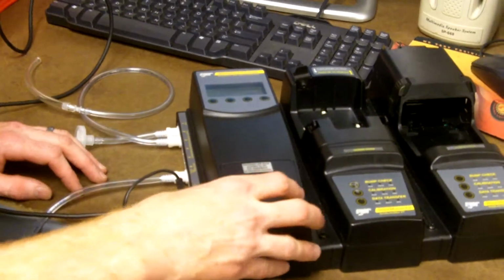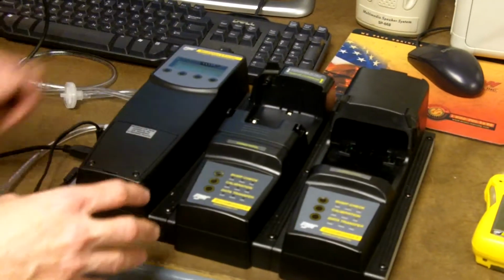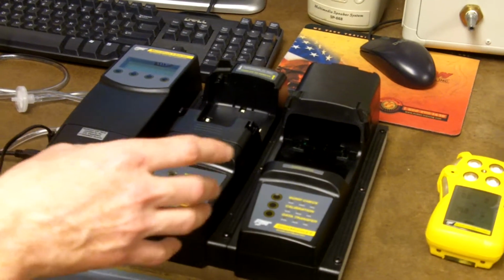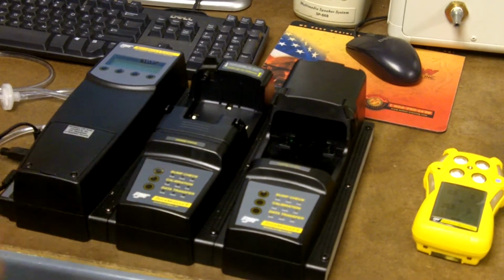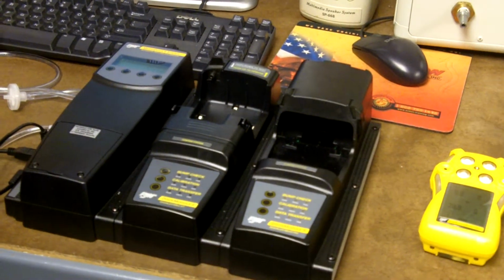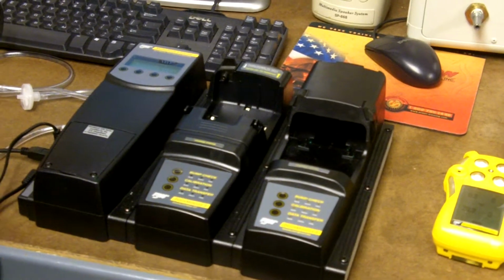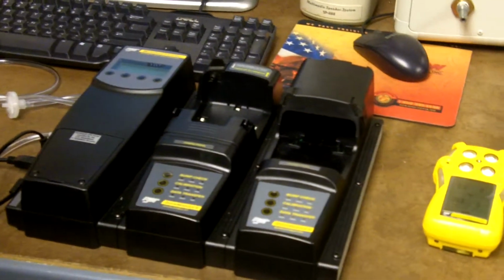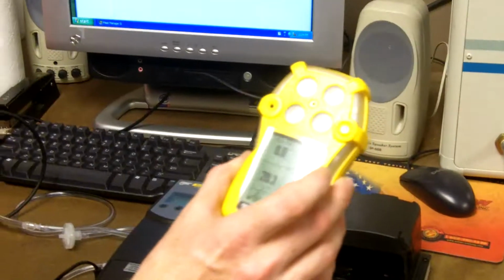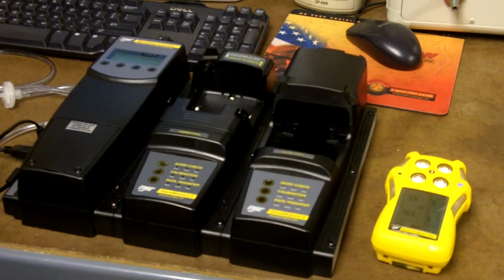So when you do calibrate your gas detectors, which would be by default once every 180 days, it'll have alarms letting you know that you're getting close to it. And when you do your checks, it'll say how many days. This particular one, I think it said 171 days until it needs its next calibration.